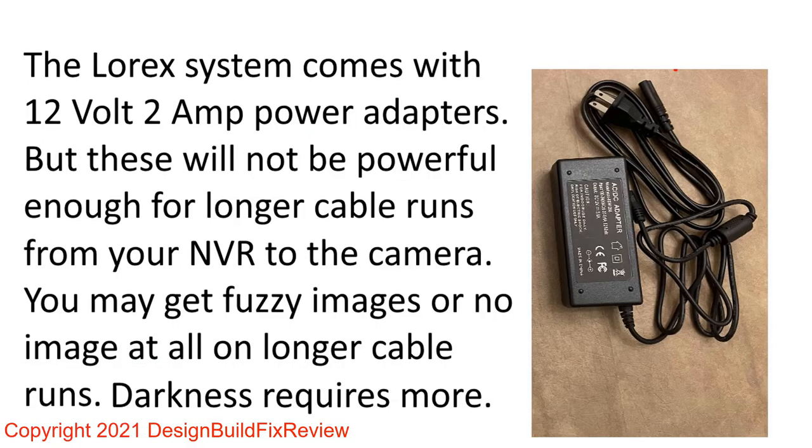In the Lorex system, it comes with a 12-volt 2-amp adapter, and each adapter powers two cameras. So if you have six cameras, you'll have three adapters. What happens is on longer cable runs — the standard cable run is 60 feet — if you add 100 feet or combine runs to get 120 or even 200 feet, the longer the cable run, the more power that camera requires.